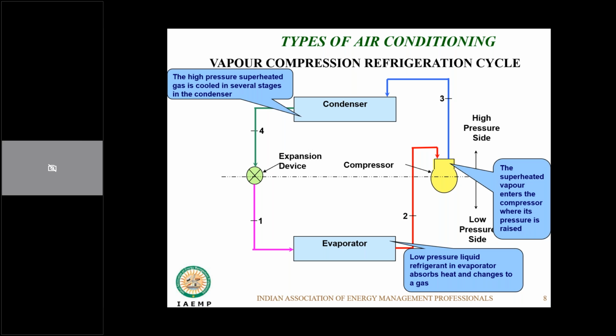Normally for an F22 circuit, the discharge temperature from the compressor is somewhere around 55 degrees centigrade. As it comes into the condenser, we have ambient air flowing if it's an air-cooled system, or if it's a cooling tower, we have water flowing through the tubes to cool this refrigerant. As it comes to almost ambient temperature, in a water-cooled case around 35, 38, 40 degrees centigrade, if you have an ambient of around 35 degrees centigrade, this high pressure, high temperature refrigerant condenses and becomes liquid at high pressure. It is now in a liquid form because the basic property of this refrigerant is that when it reduces its temperature, it condenses and forms a liquid.